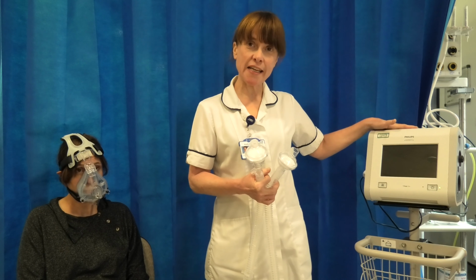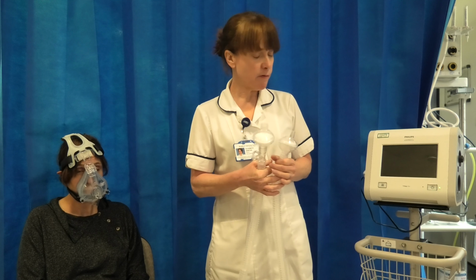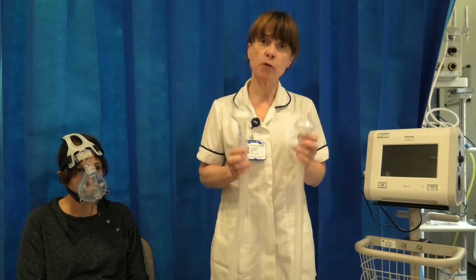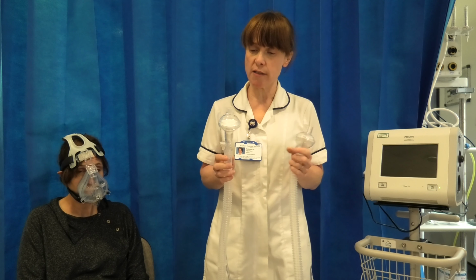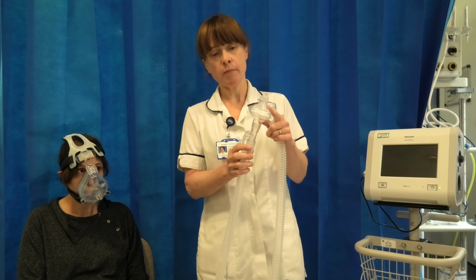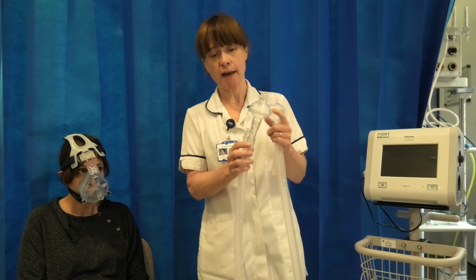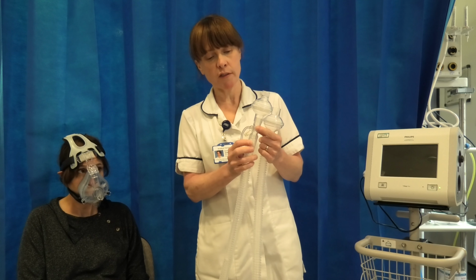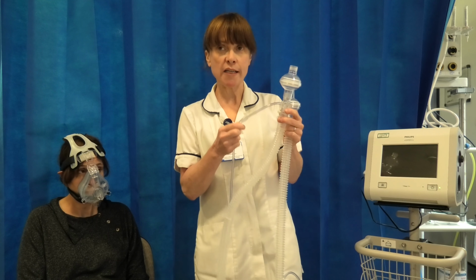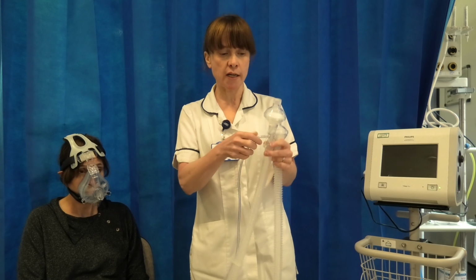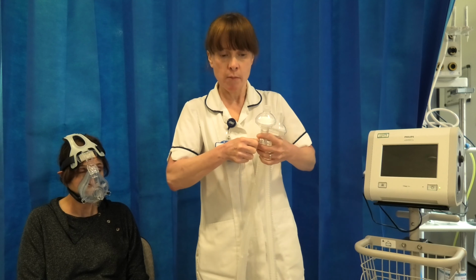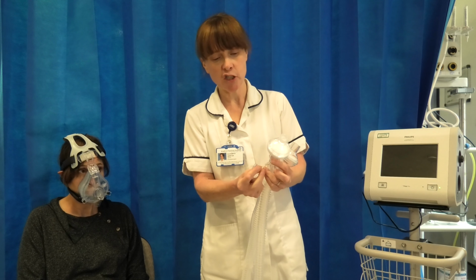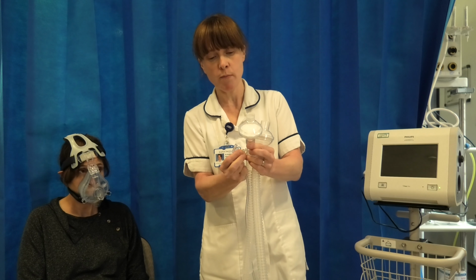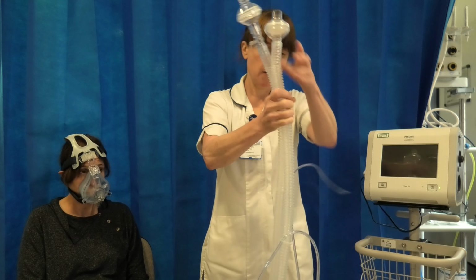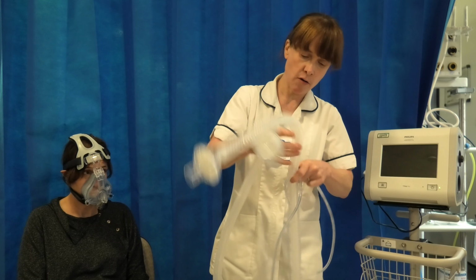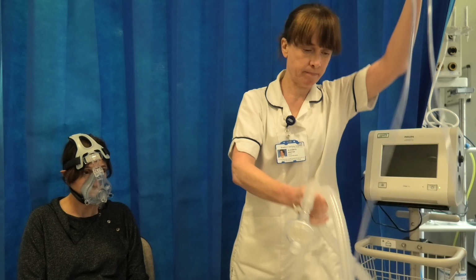Introducing the Trilogy Evo. So for the Trilogy Evo, when we're setting it up, initially we use a dry circuit or a passive circuit. So you can see we have a filter that is always at the patient end before your exhalation port. This is your exhalation port. We don't need a pressure line for this machine, so the pressure line needs to come off before you set up the Trilogy Evo. I'm just going to call it the Evo. So you make sure that you cap that off. And you take the pressure line off and you can discard that.